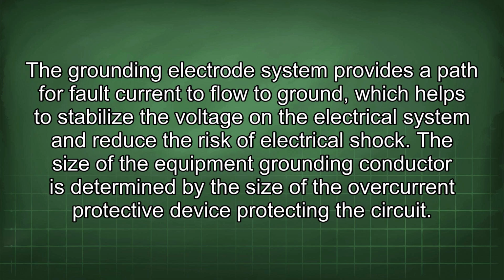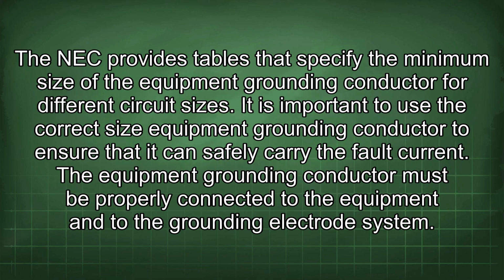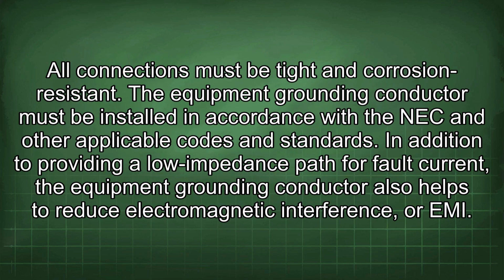The size of the equipment grounding conductor is determined by the size of the overcurrent protective device protecting the circuit. The NEC provides tables that specify the minimum size of the equipment grounding conductor for different circuit sizes. It is important to use the correct size equipment grounding conductor to ensure that it can safely carry the fault current. The equipment grounding conductor must be properly connected to the equipment and to the grounding electrode system. All connections must be tight and corrosion resistant. The equipment grounding conductor must be installed in accordance with the NEC and other applicable codes and standards.